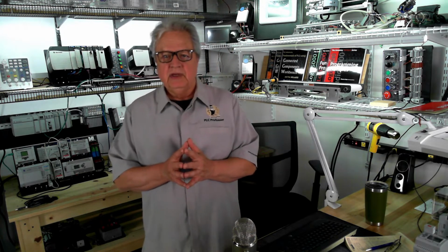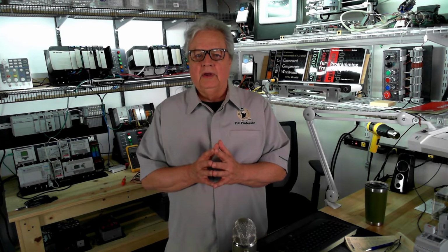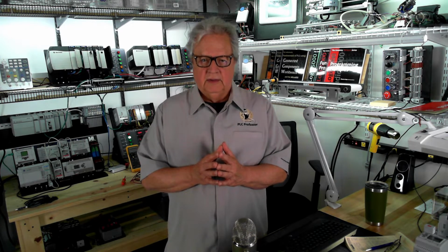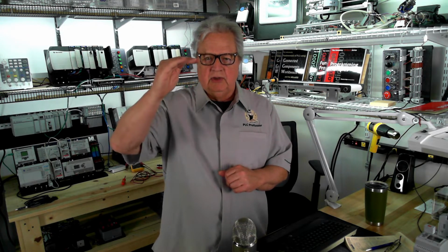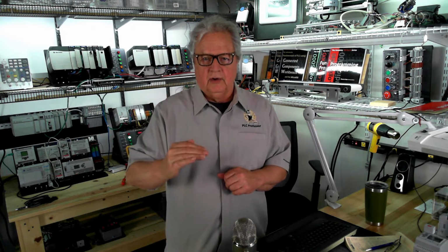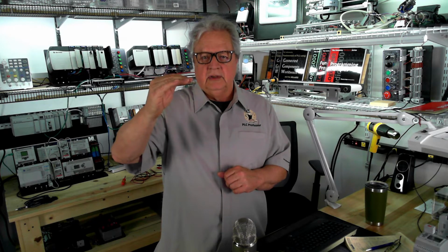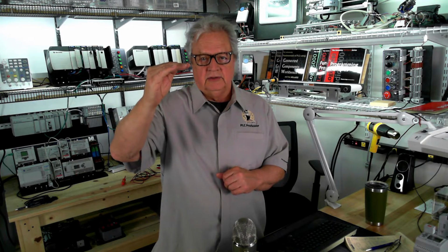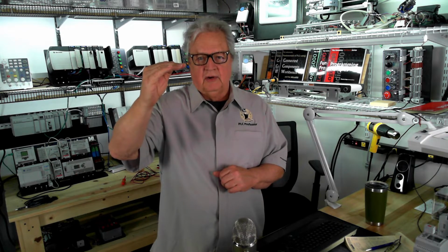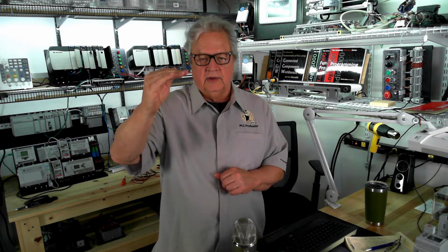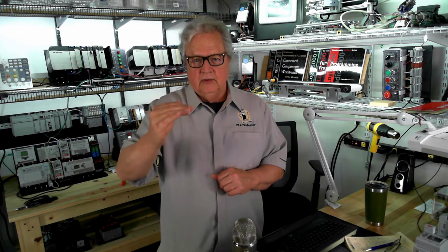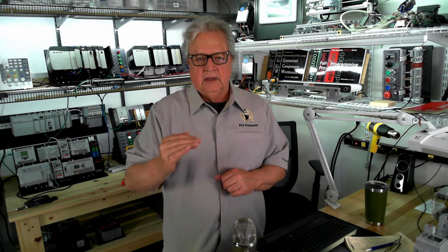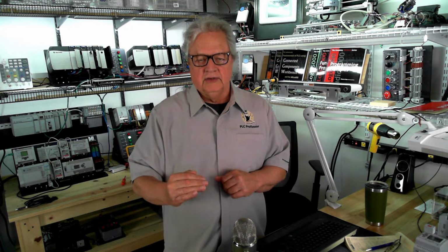And the concept is to avoid asynchronous behavior, meaning when the program starts to execute, rung after rung after rung, in the rungs, it is examining, on occasion, input bits. In other words, bits in memory locations that are associated directly with a screw terminal, an input. And it continues to look at those different inputs as it goes down through the logic.